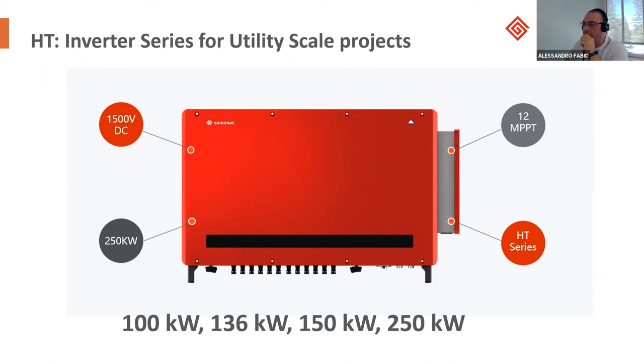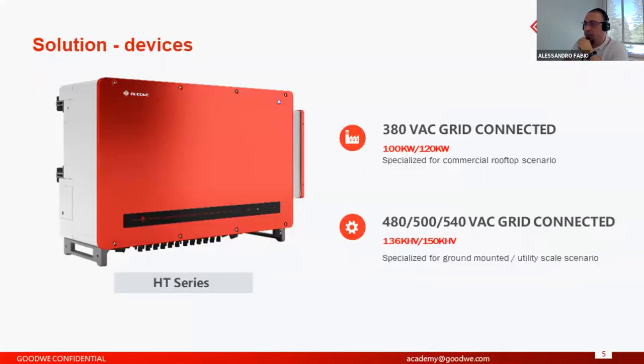The HT series has external connection cable for the DC side with 12 MPPT. In this case, for example, the HT series is 380 volt three-phase grid connected, and the 100 and 120 kilowatt models are specialized for commercial rooftop scenarios. For utility scale scenarios, connected with the transformer, we have another series with 480, 500 and 540 volt grid connection, also for connecting to high voltage or middle voltage transformers.